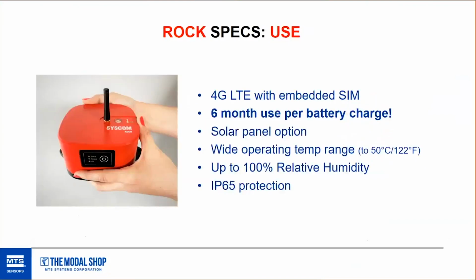Kind of gives you a handle of the actual size of the unit. But remember, the modem and the data plan are built in, and this thing lasts forever. Six months is the stated spec, but SYSCOM has a published paper where it substantially exceeds six months, and it's set up with real-life measurements: 1,000 hertz sampling, frequency up to 315 hertz, triggering at 1 millimeter per second on all axes, pre and post event recording, background measurements, and SCS synchronization to the software every hour.